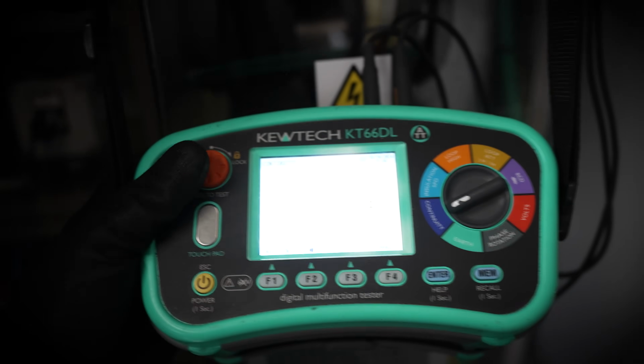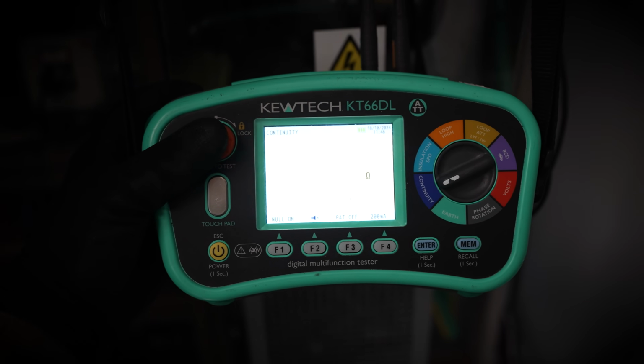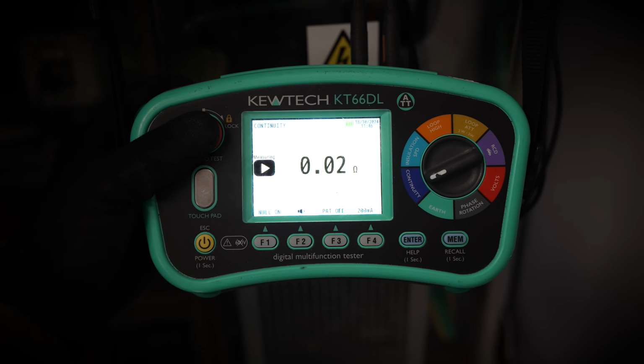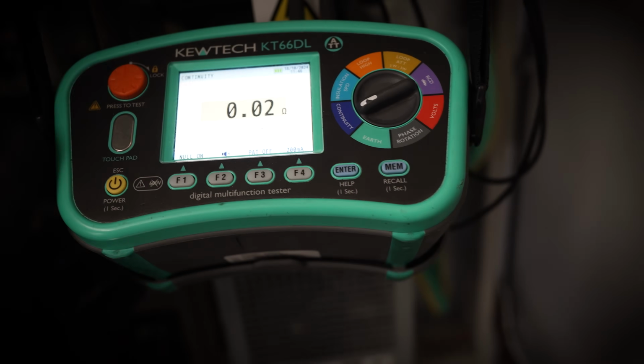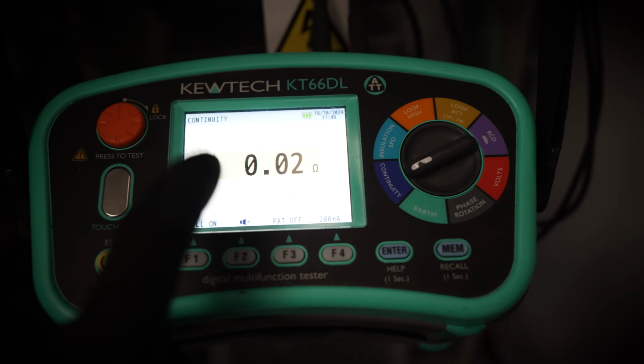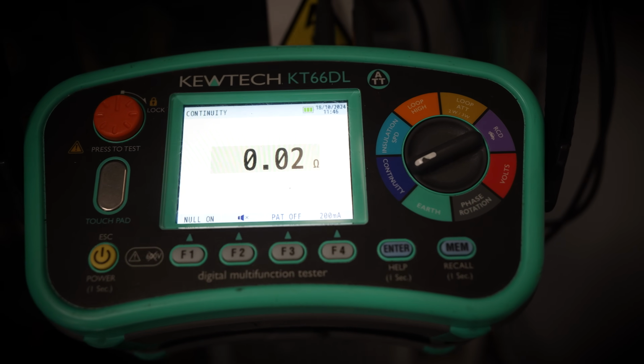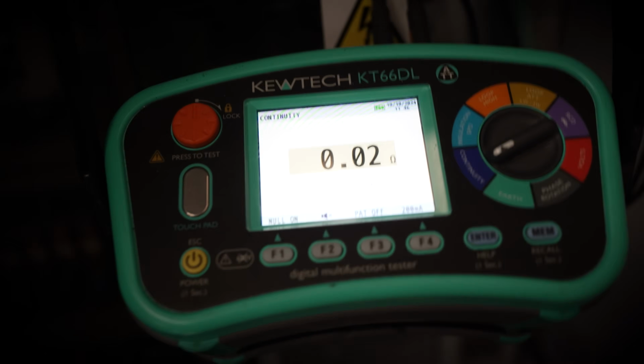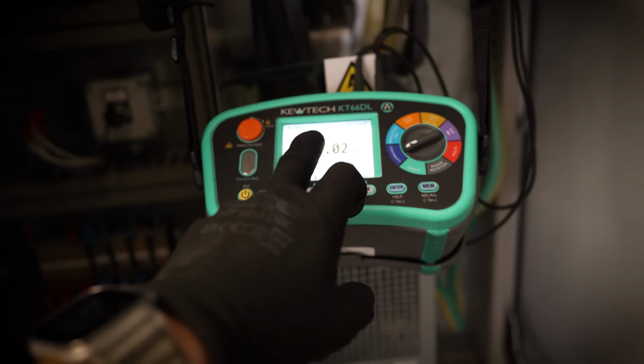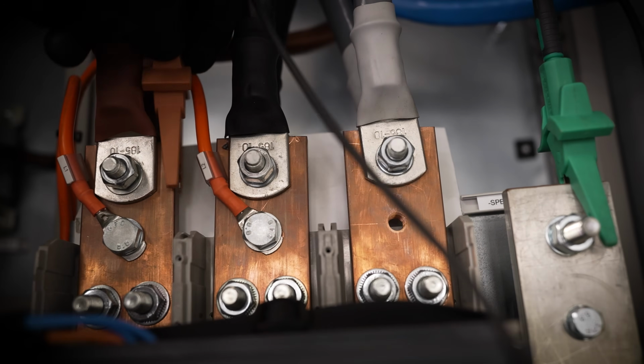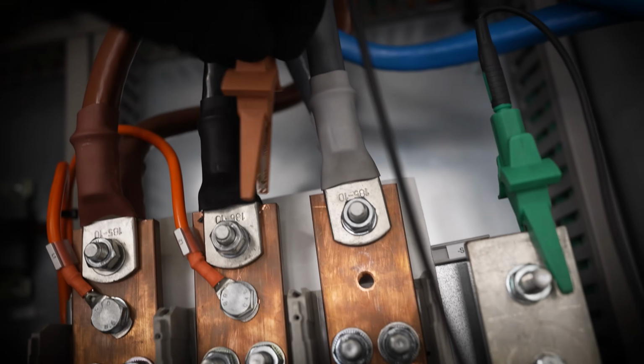All right, so back up here. I want to make sure I'm on continuity. Hopefully we get a result. There we go, 0.02. That is just what we wanted. Yeah, perfect. So now I'm going to jot that down for L1. Move this over. We can go and test L2.